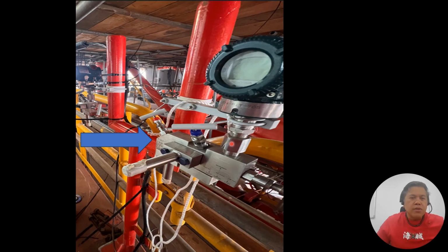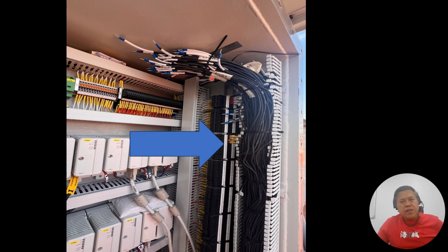All right. So this is some of the information and observations that we covered. And here is another one. This is our RIO or AUX cabinet. And basically during the installation, this is our compartment. This is our trunking. When the field instrument cable wire is to be installed here, since the trunking is small, all this cable overlaps, so it will not fit in our trunking. So this is an observation as well.